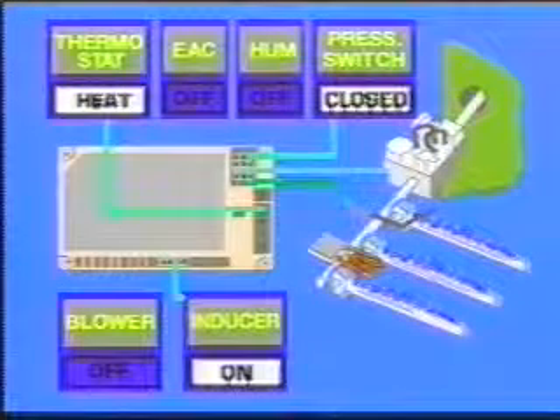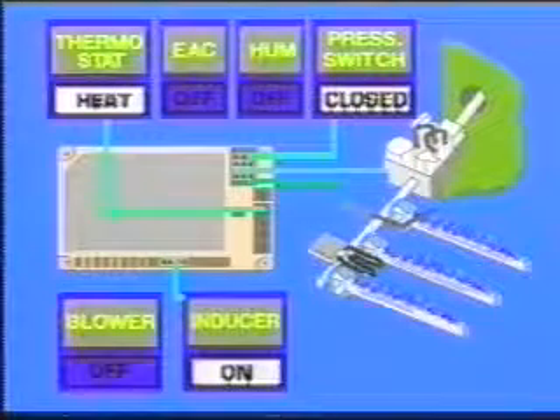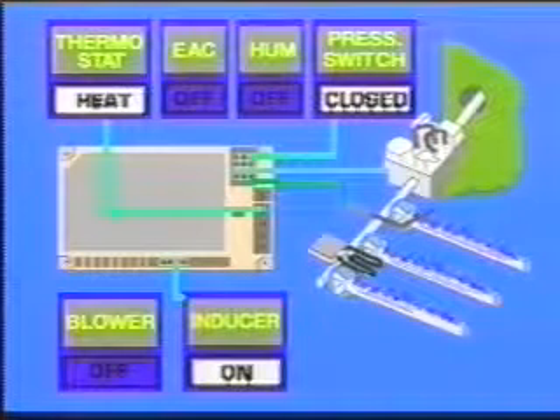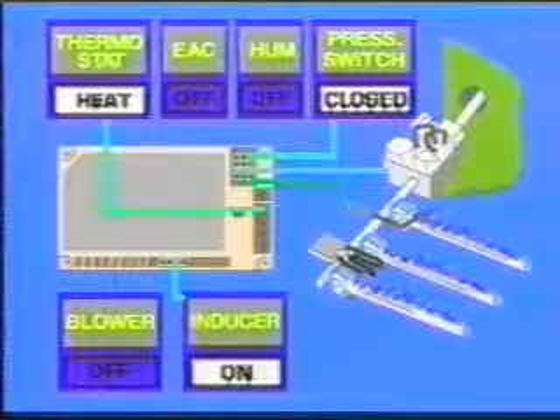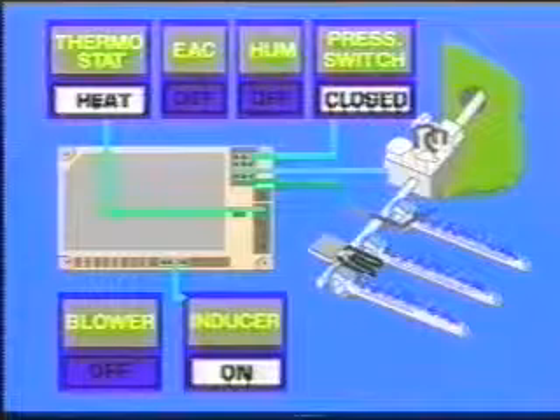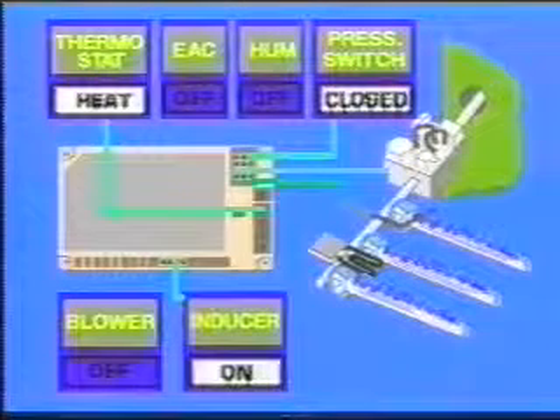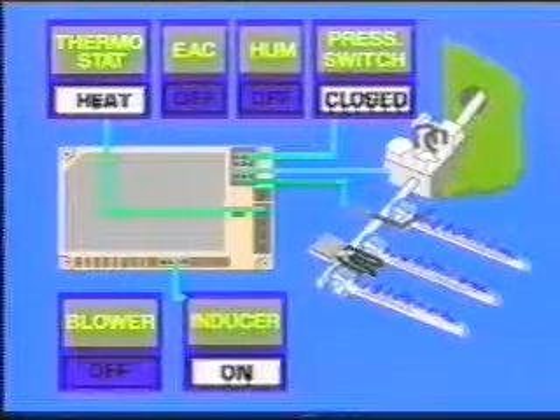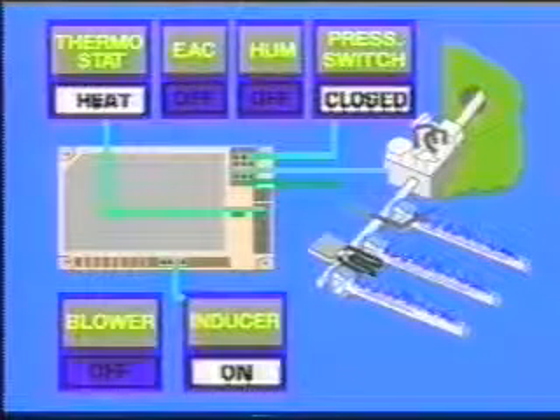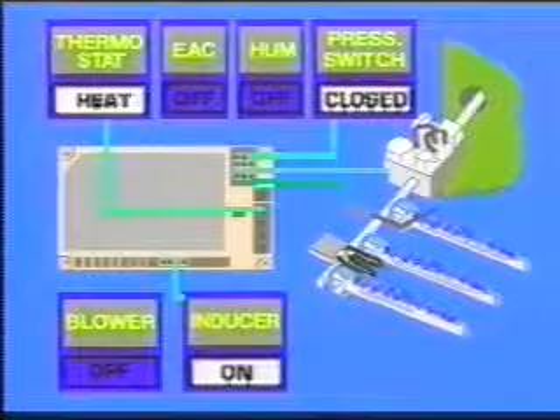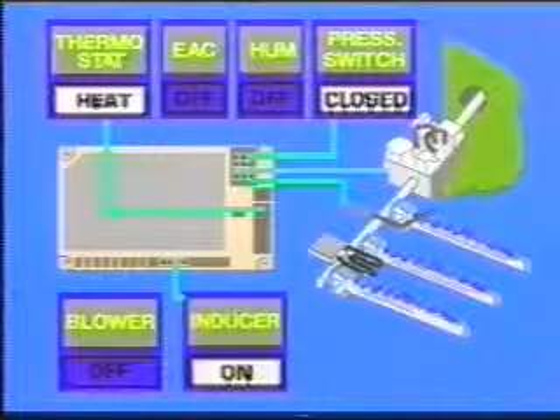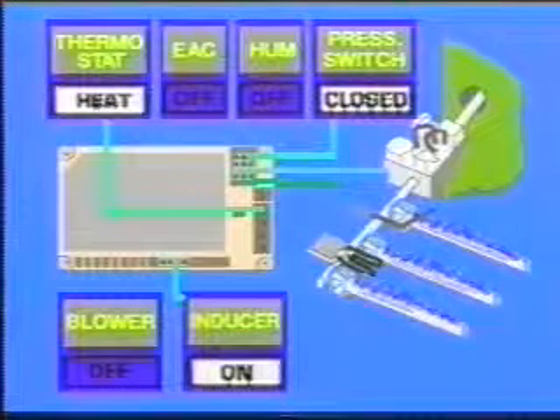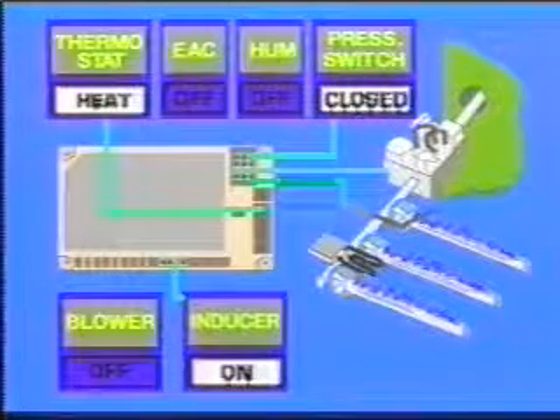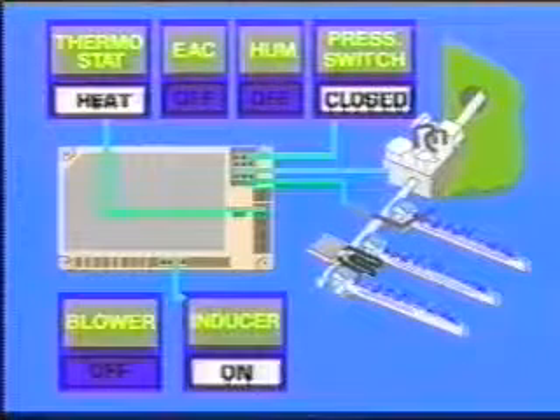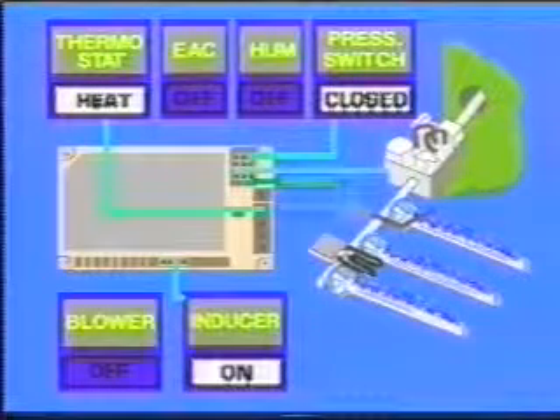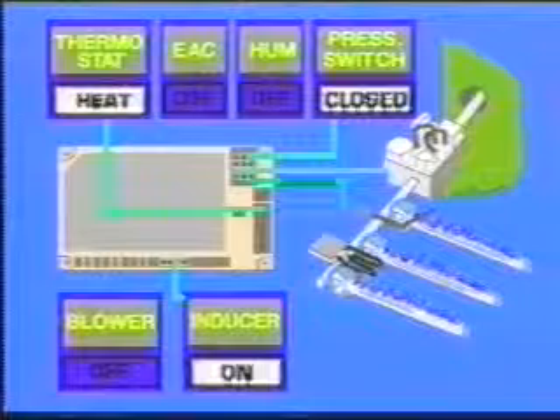The igniter is de-energized 3 seconds before the trial for ignition time has elapsed. Once ignition is accomplished, the flame is sensed by the flame sensor and the gas valve is energized open to allow gas flow. If flame is lost, the gas valve is de-energized within 2 seconds. This helps the flame signal to get established when the burner is cold. Once burner flame is established, the delay to fan on period begins.